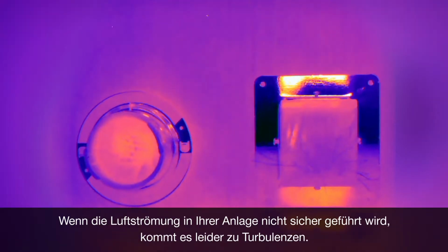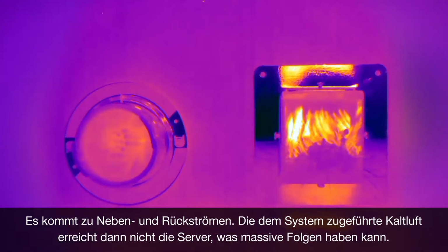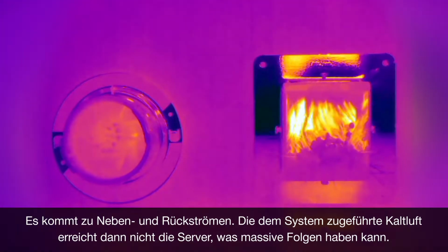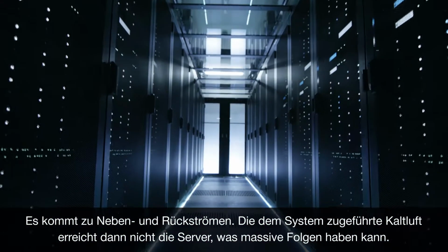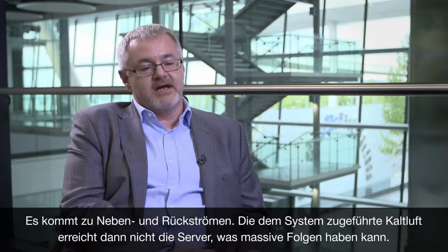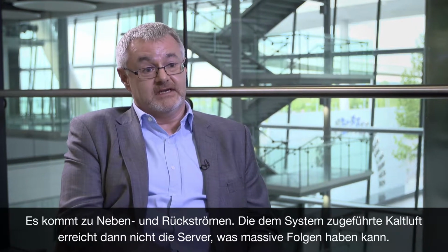If you haven't secured your airflow within your facility, you will unfortunately have turbulence. You can have bypass air and recirculation air, where the cold air you're pushing into the system doesn't reach the servers, and in some cases it can have a massive impact on your facility.